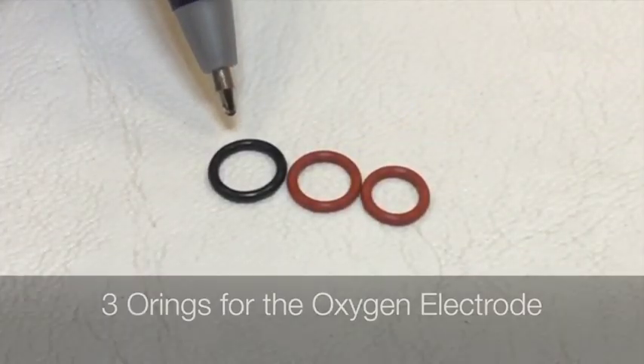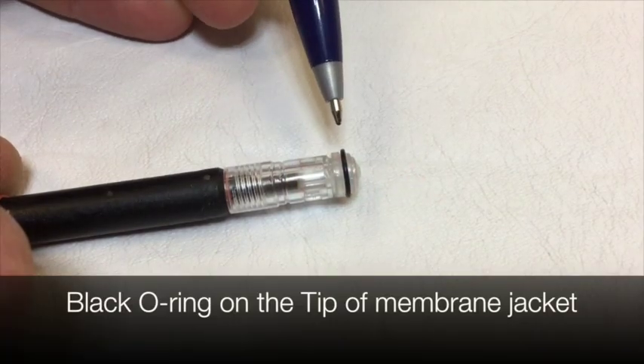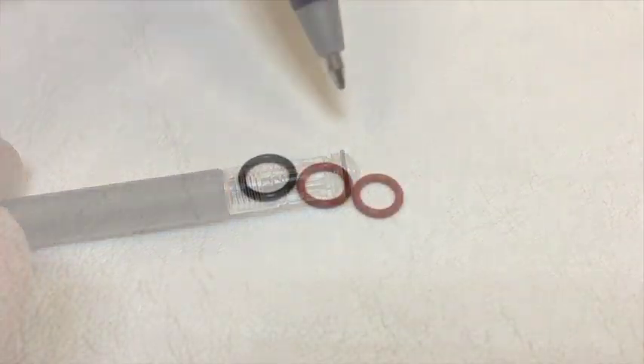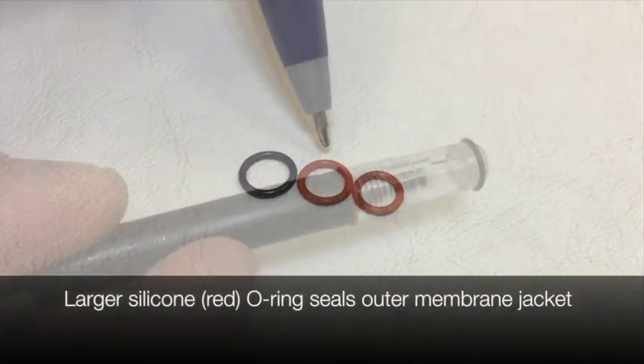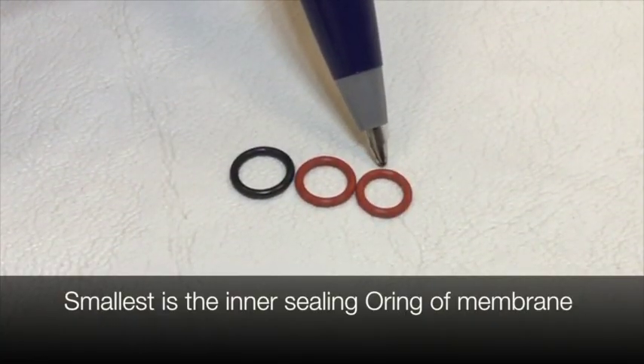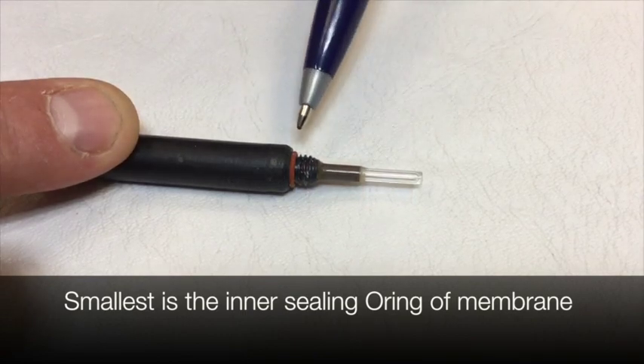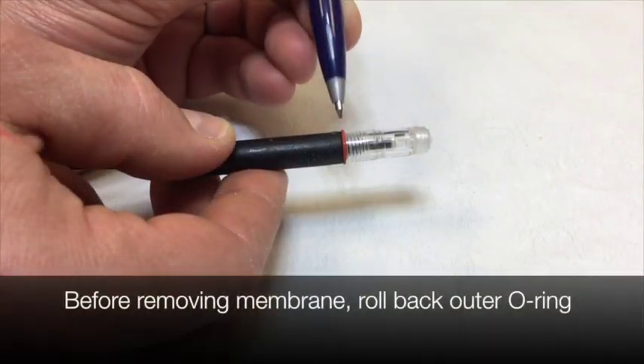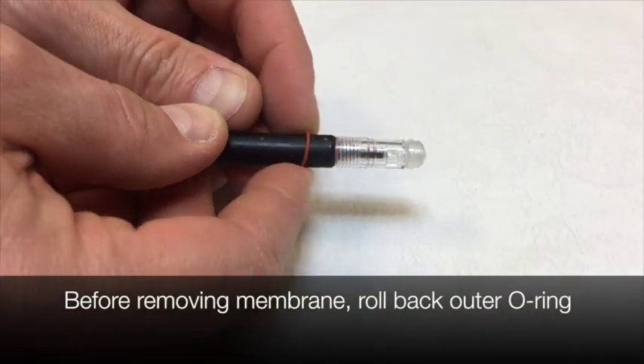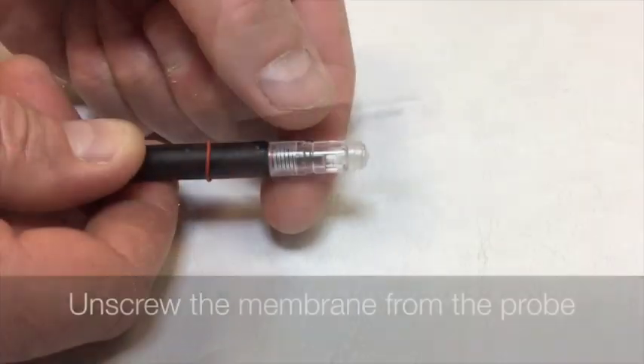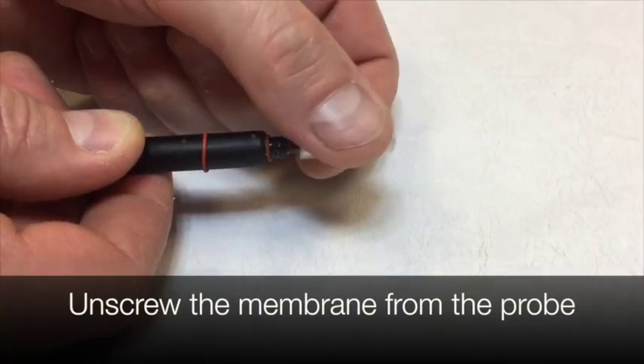There are 3 O-rings for your oxygen electrode. The black one goes on the tip of the oxygen electrode. The larger of the silicone O-rings seals the outside of the membrane jacket. The smallest of the silicone O-rings is the inner seal for the membrane jacket. Before removing the membrane jacket, roll back the larger silicone O-ring. Unscrew the membrane from the probe.